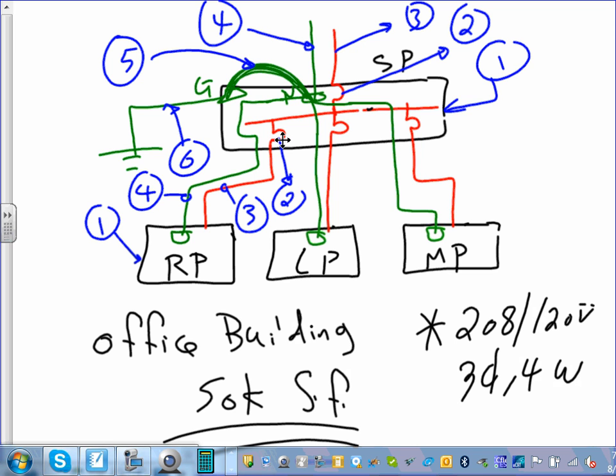Then number 2 is the circuit breaker that protects the panel, the receptacle panel. And also, we're going to have one for the lighting panel and one for the mechanical panel, right? Number 3 is going to be the conductors, the feeders, the size of the feeders, right? The same thing for receptacle, light, and mechanical. Number 4 is the neutral. With every feeder to a panel, guys, comes a neutral. You have to have a neutral. Now, does everybody understand what a 3-phase 4-wire system is? When you design commercial, you almost always run so-called 3-phase 4-wire. So, my friend, the first 3 conductors, the 3 wires, are the hots, A, B, C, phase 1, 2, 3, and what's the last one? The neutral.